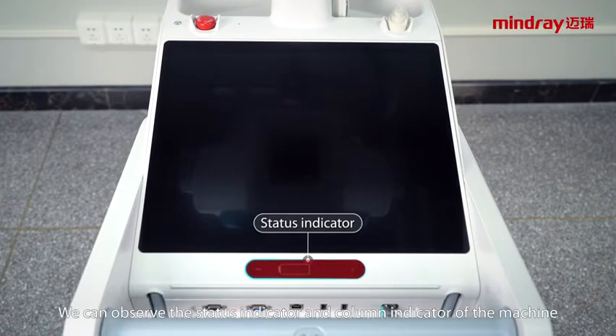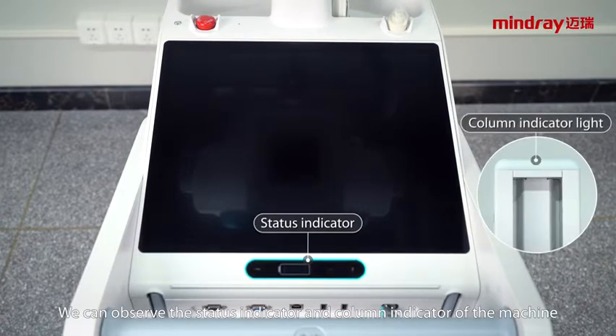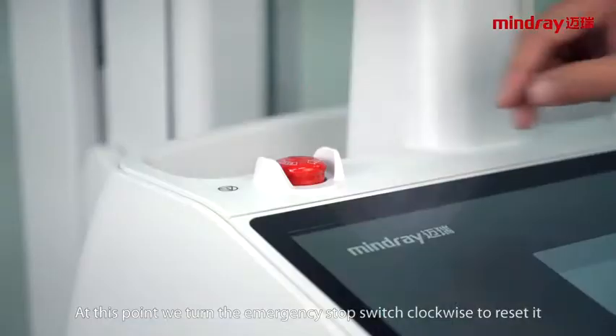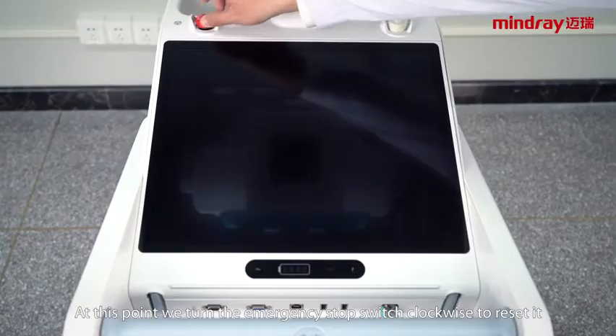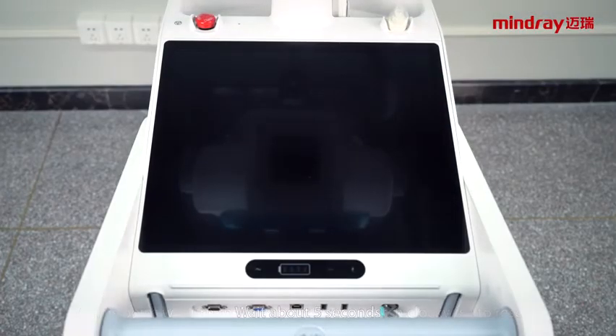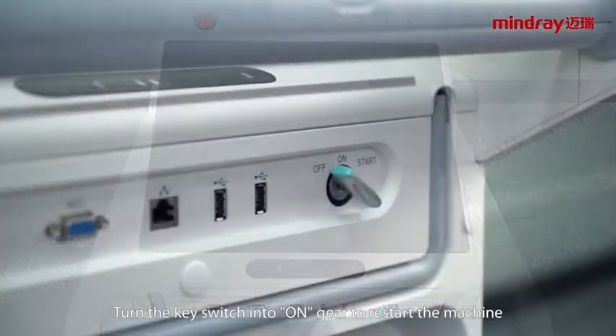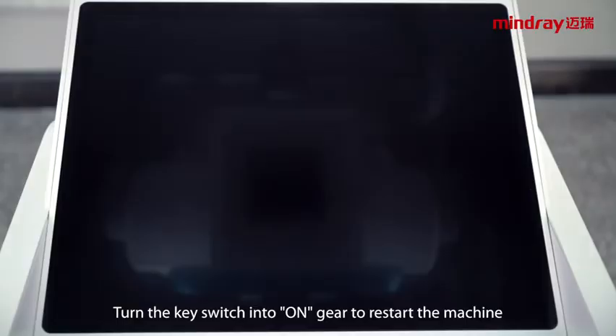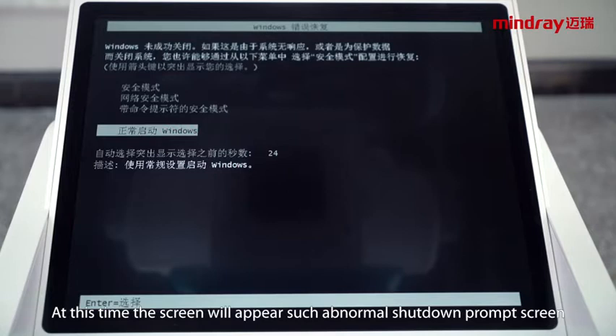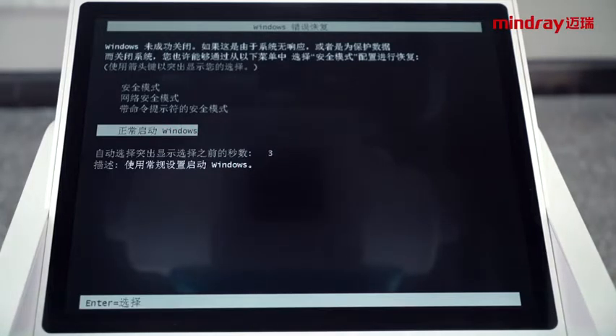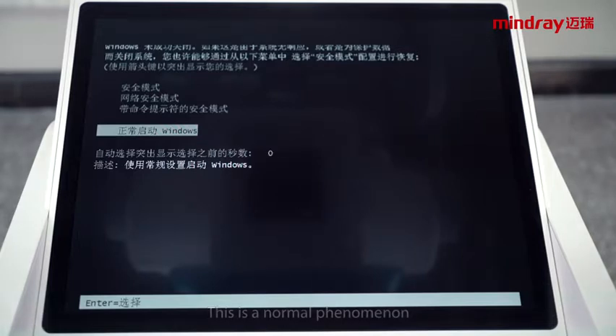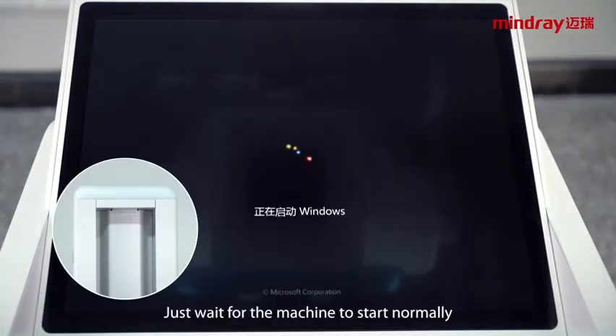We can observe the status indicator and the column indicator of the machine. When you see the light completely off, it means that the forced power shutdown is successful. At this point, we turn the emergency stop switch clockwise to reset it. Wait about 5 seconds. Turn the key switch into on gear to restart the machine. At this time, the screen will show an abnormal shutdown prompt screen. This is a normal phenomenon. Just wait for the machine to start normally.